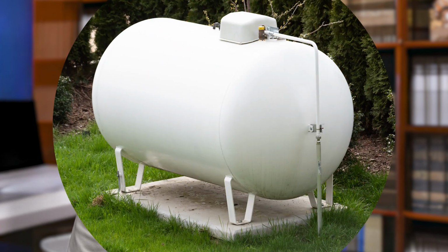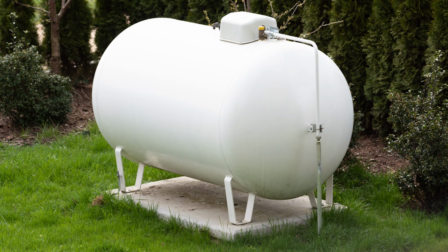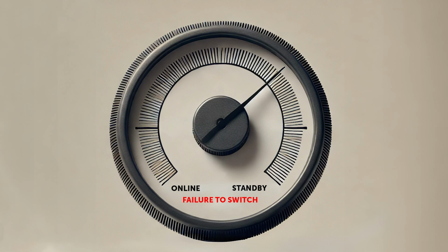Generators can be finicky, requiring ongoing maintenance to ensure proper operation. They also have a large physical footprint and mechanical infrastructure due to the need for fuel storage and resupply. Their biggest drawback is they operate in standby mode. There is always the risk they will simply fail to start up when needed, and for true non-interruptible power, they must be combined with battery storage or other UPS technology to provide power during their slow startup and transfer time if you want continuously smooth power.